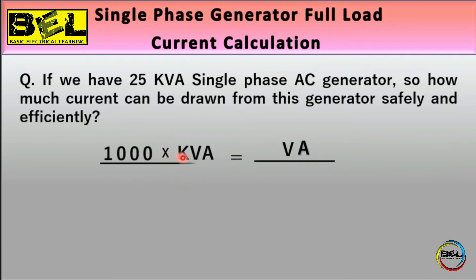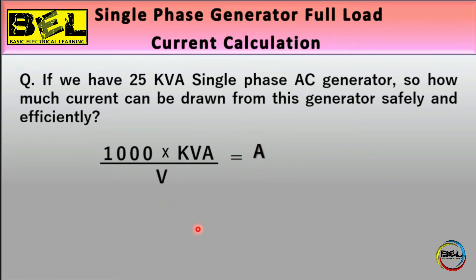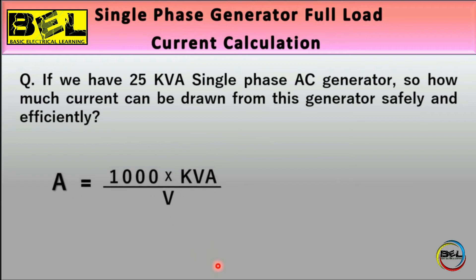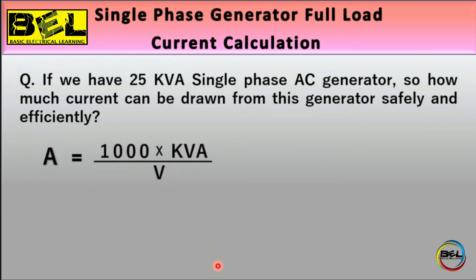Rearranging the formula: multiply both sides by 1000 and divide by voltage. The result is: Ampere = (1000 × kVA) / Voltage. Now we have the values of kVA and voltage, so let's calculate the total current.